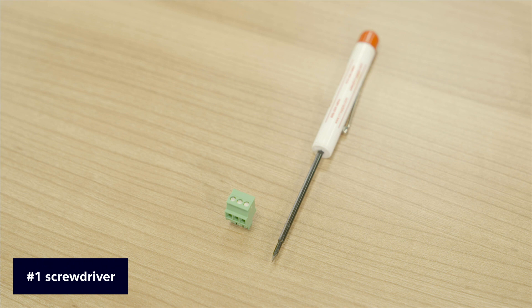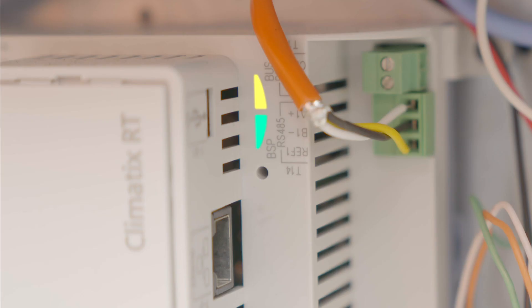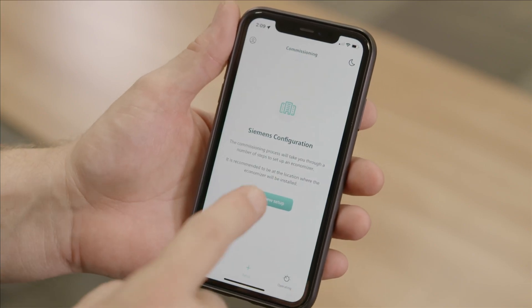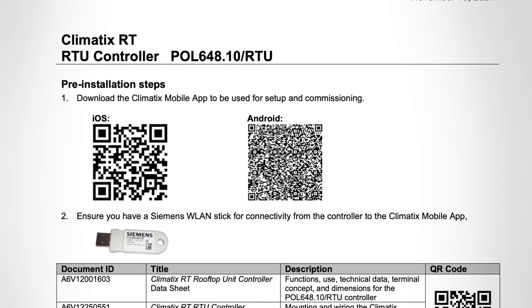Here you will use the number one screwdriver. Before commissioning, be sure to have your distributor key available. This key is provided by your tenant administrator. Power on the RTU and check that the Climatix RT controller lights are green. On first connection, the connection to the cloud may take a few minutes. Now open the Siemens Climatix mobile app. The app is available in the Google Play Store and Apple App Store. It can be quickly accessed with the QR code on the Quick Install Guide. Plug the Wi-Fi stick into the controller to start your commissioning. Now follow the steps in the app.